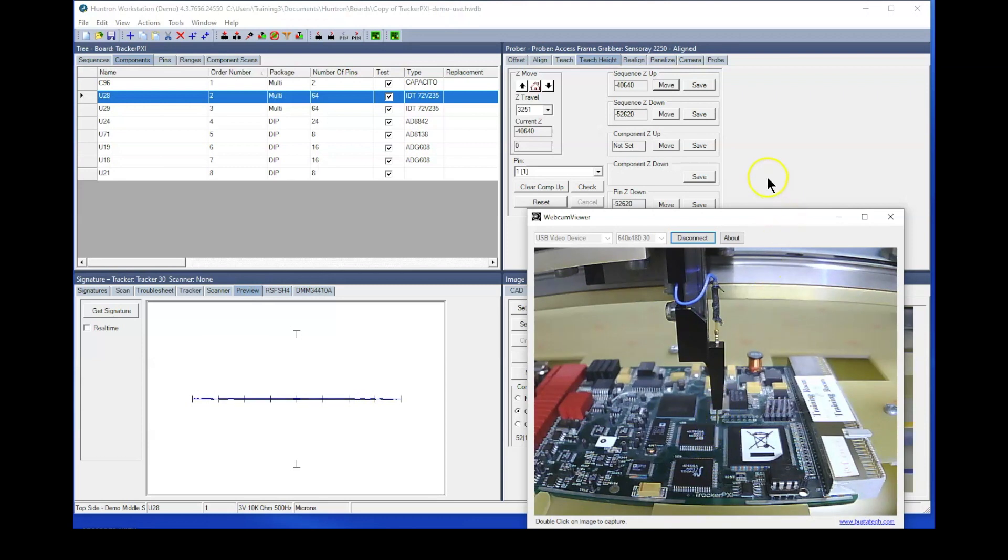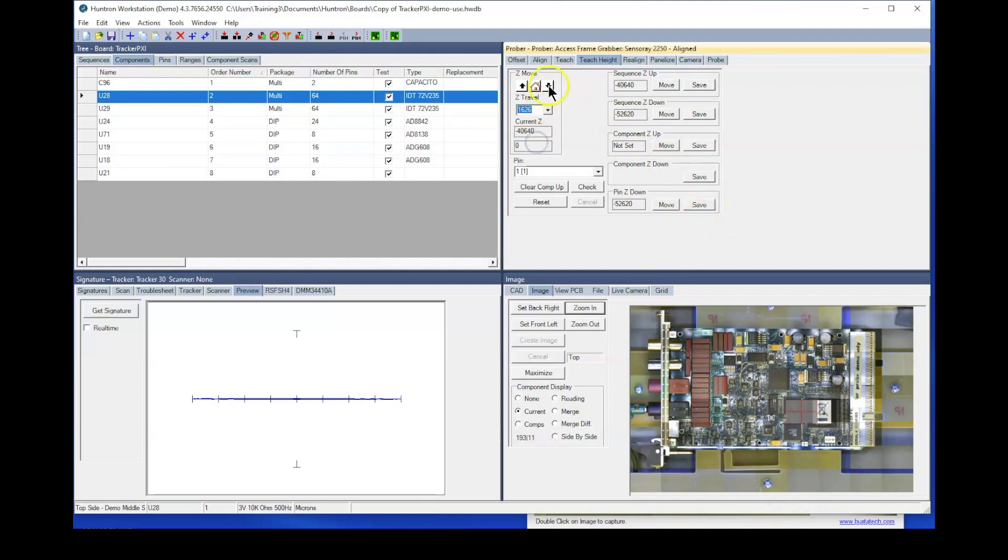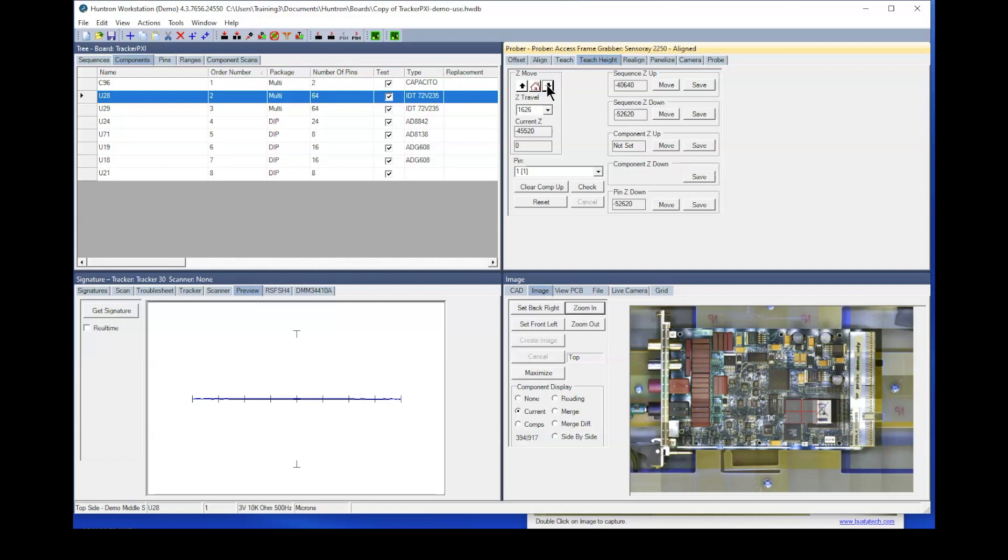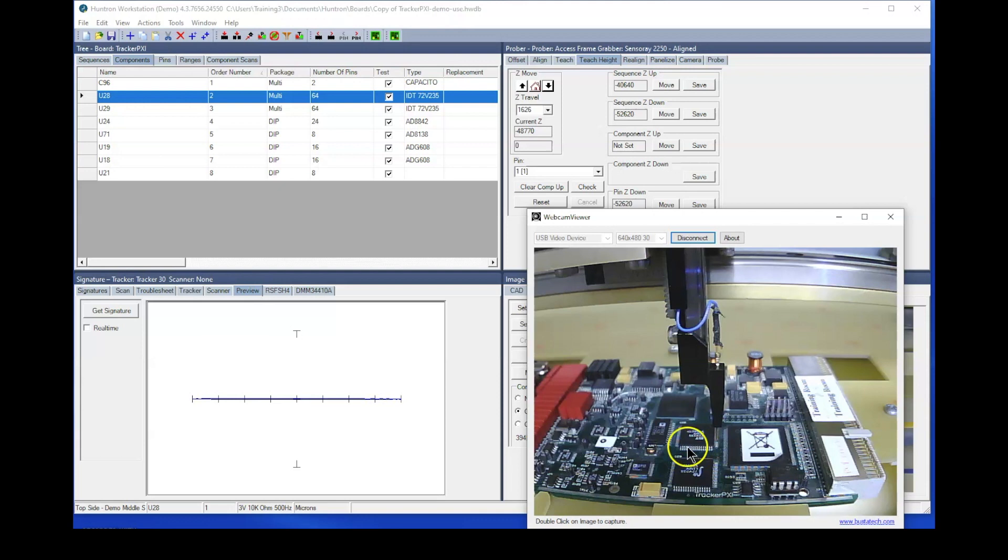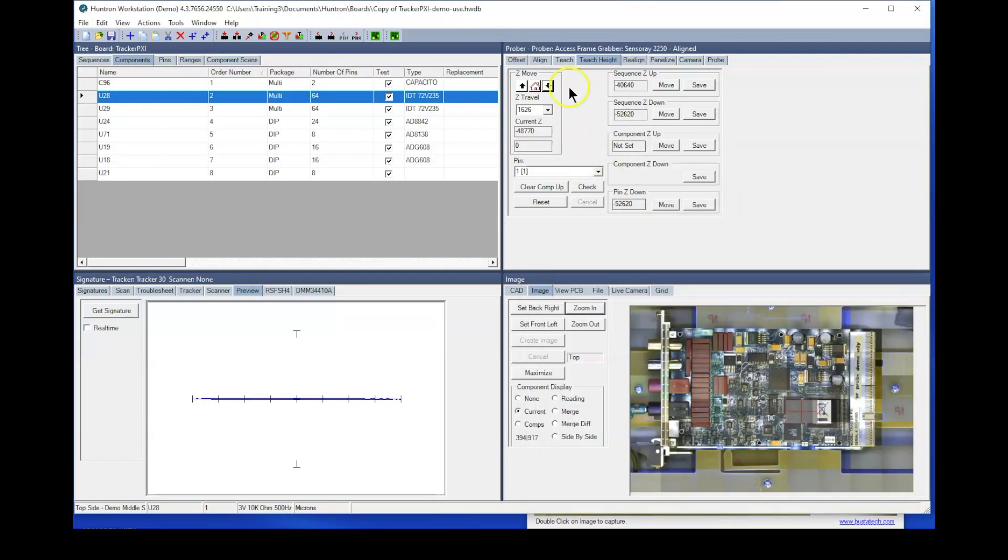But in reality, what I really want to do is have this probe at a much lower level. So in the teach height, you can select, first of all, let's move our probe down to where we want it to be. I'm going to go ahead and modify the probe down. Let me show you the video. See, I'm going to put it down right about here, maybe a little bit lower. Back to the video. So you can see I've got it quite a bit lower. The thing I want to make sure is that when the probe goes from one side of the IC to the next side, that it gets high enough to get over the corner of the component. And that looks pretty good. I've got maybe a millimeter or two of clearance above the pin to the over the body of the component. So what we'll do is in this teach height, we'll save that as our component Z up.